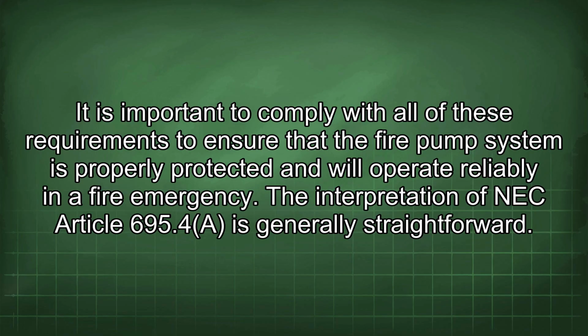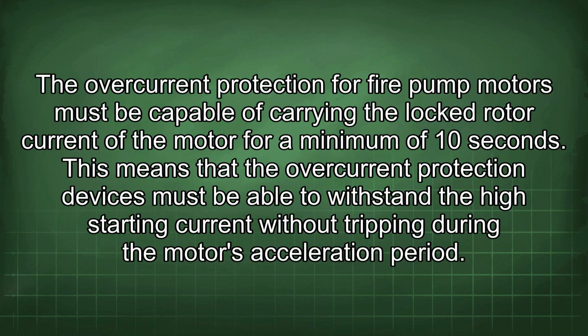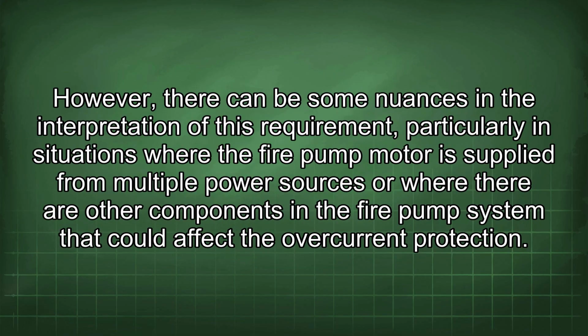The interpretation of NEC Article 695.4 is generally straightforward. The overcurrent protection for fire pump motors must be capable of carrying the locked rotor current of the motor for a minimum of 10 seconds. This means that the overcurrent protection devices must be able to withstand the high starting current without tripping during the motor's acceleration period. However, there can be some nuances in the interpretation of this requirement, particularly in situations where the fire pump motor is supplied from multiple power sources or where there are other components in the fire pump system that could affect the overcurrent protection.